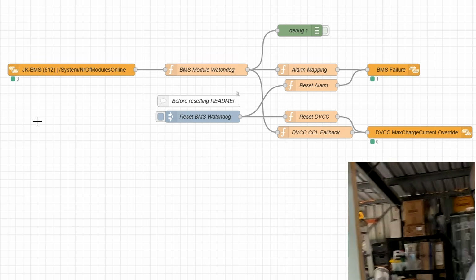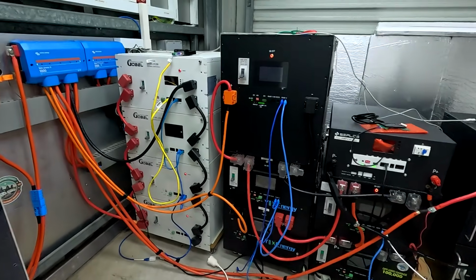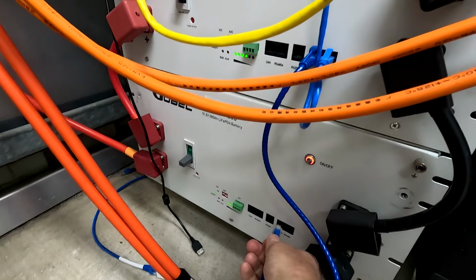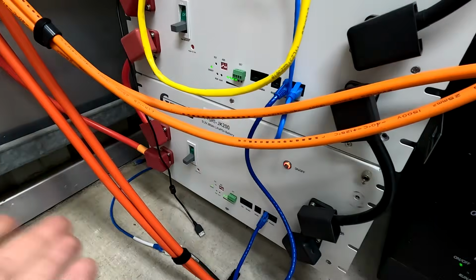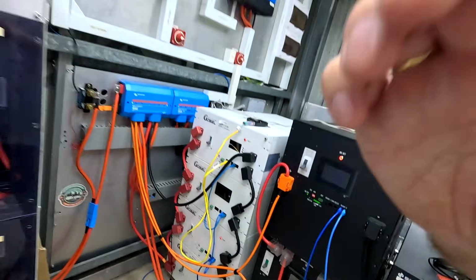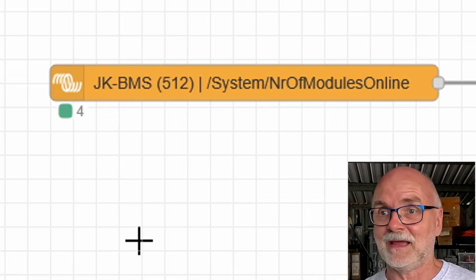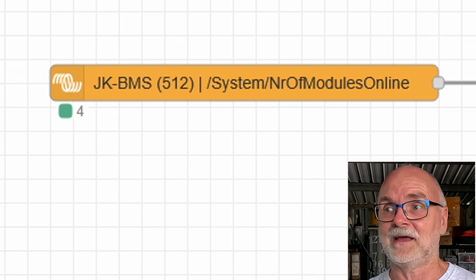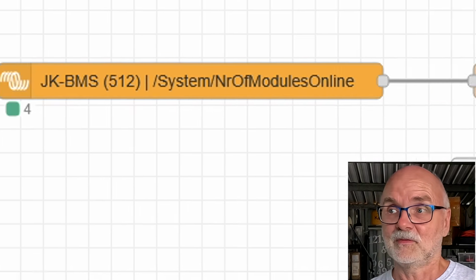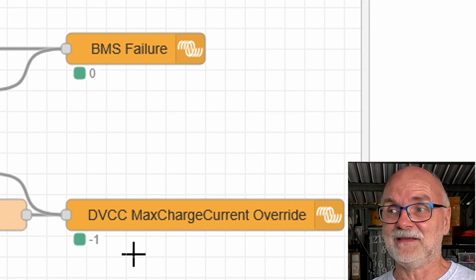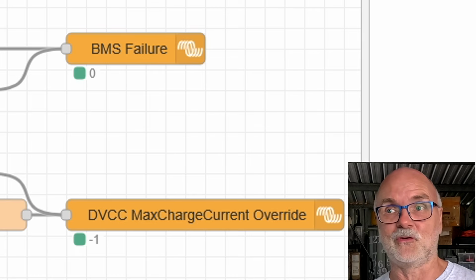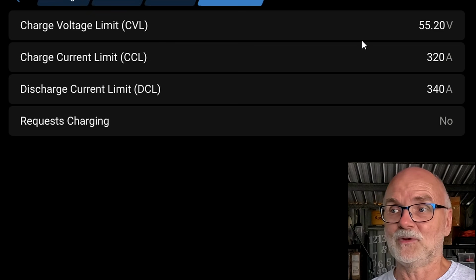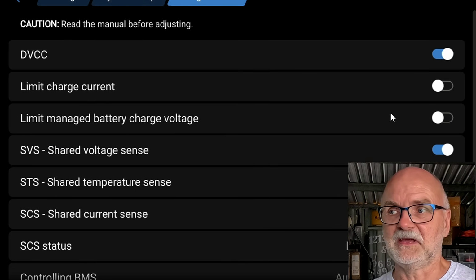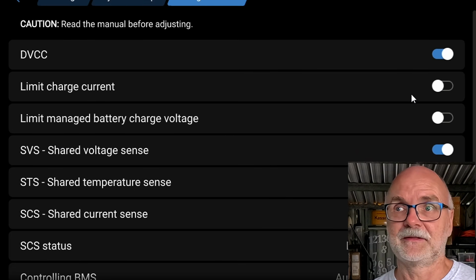So if I plug in the cable again, if it's only a temporary issue, the BMS starts responding again, which could happen if I replace the cables with longer ones with different colors or something. I temporarily only disconnect the BMS. You can see we've now got 4 BMSs online again, back to where it was. The BMS failure is on 0 and the DVCC is on -1, which is turned off. So here we are back to 320 amps, 4 BMSs times 80. Here it is turned off again, no charge limit.